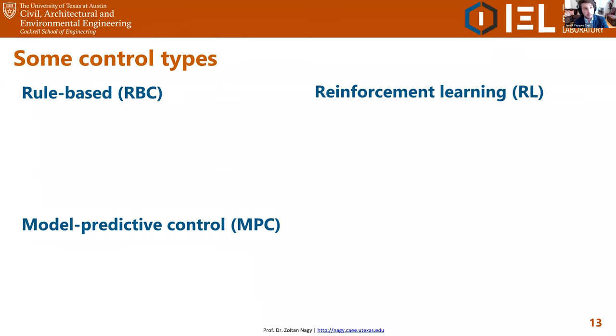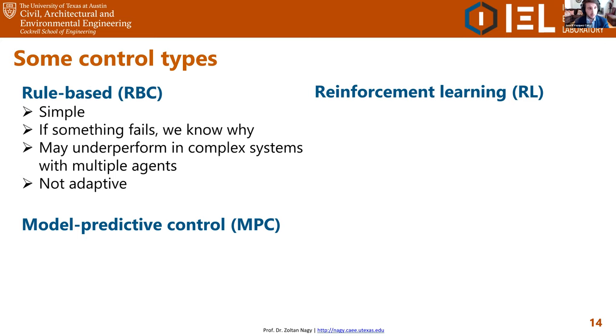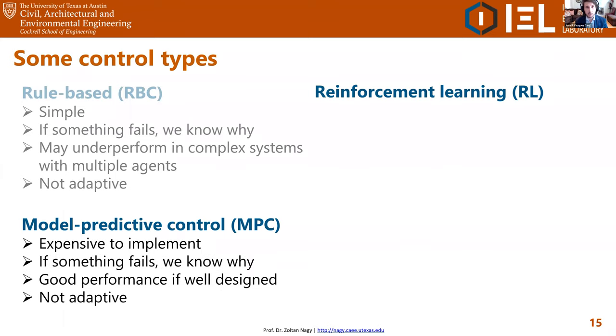There are many different types of controllers. The rule-based controller is the industry standard — based on if-else statements that take control actions depending on conditions, such as whether to store or release energy. It is simple and inexpensive to implement and transparent when something fails. However, it is not adaptive, so if the system changes we need to manually redesign it, and it may underperform in complex or multi-agent systems where multiple agents share a common goal.